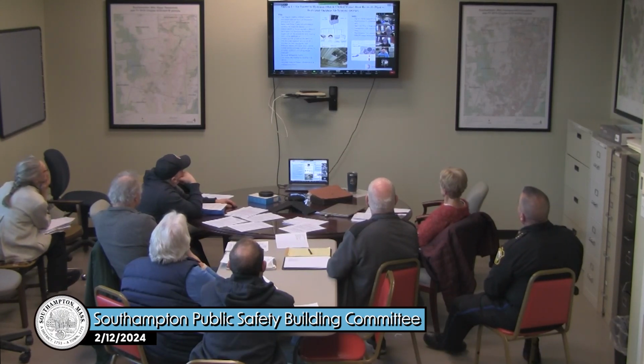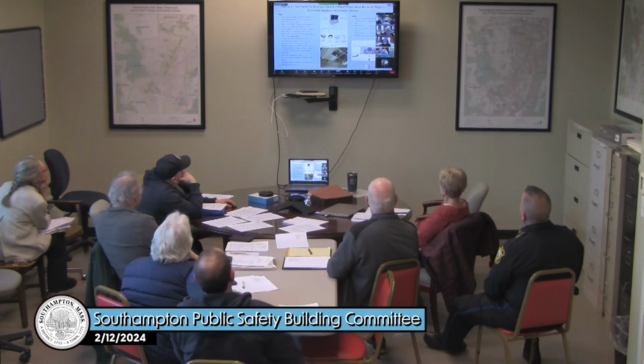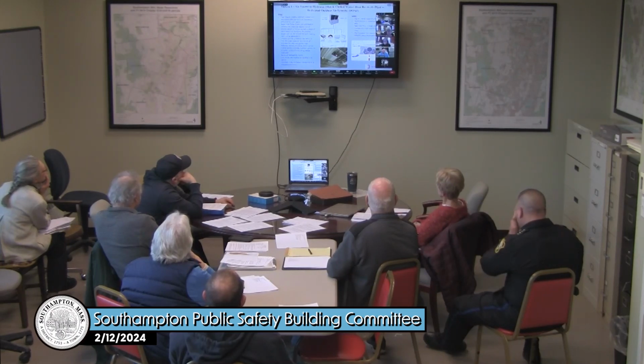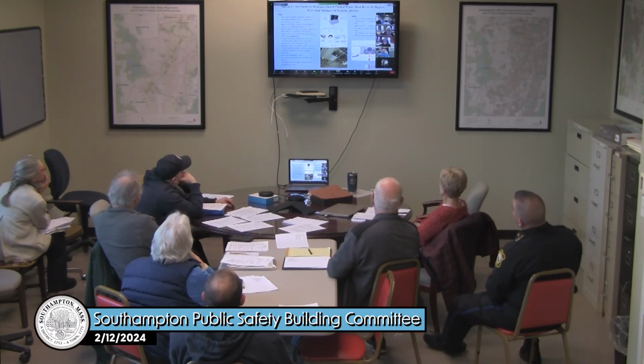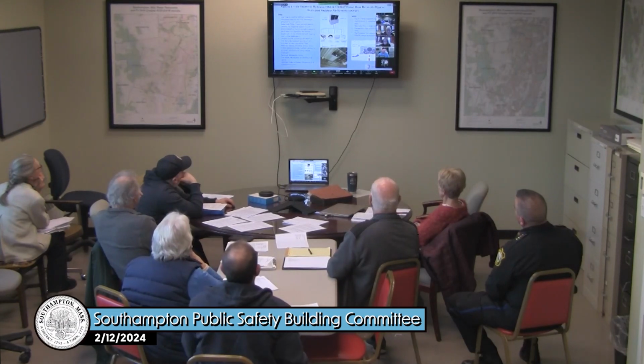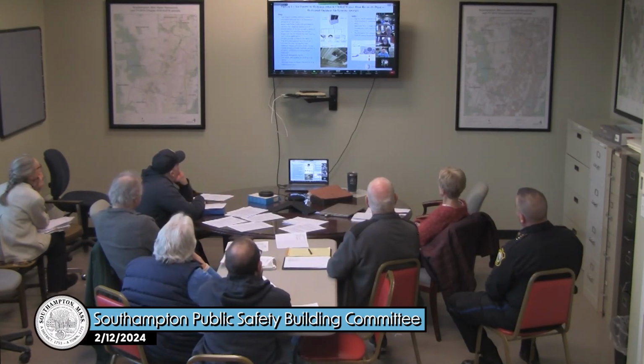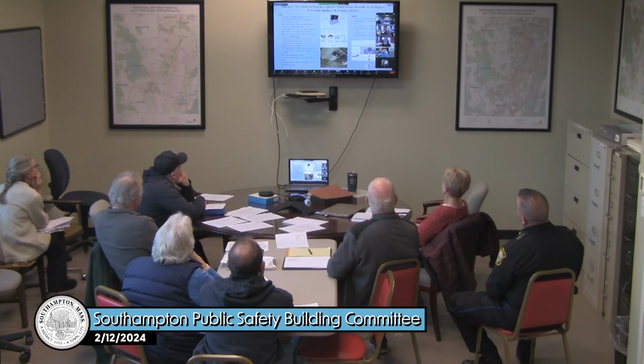And because you're just providing ventilation air, that results in smaller ductwork. We're recommending, I think, fan coil units for this option, but you could also go with induction units. Indoor unit styles provide multiple options to fit within architectural ceilings. Reduced refrigerant piping, because there's really no refrigerant running through the building. It's just all within your chiller, so all your refrigerant is outside. You can utilize hot water heating for heating-only spaces, which is great. And there are potentially reduced future maintenance and replacement costs.